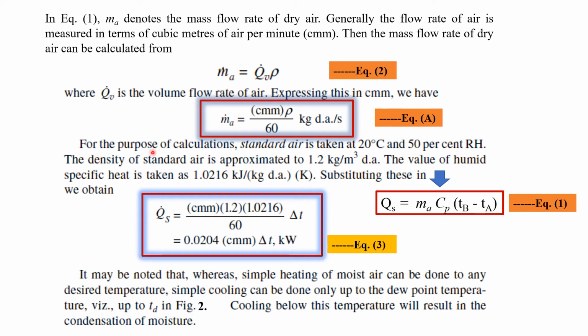Now for the purpose of calculations, the standard air is taken at 20 degrees Celsius dry bulb temperature and 50% relative humidity. The density of standard air is approximated to 1.2 kg per meter cube of dry air. The value of humid specific heat is taken as 1.0216 kilojoules per kg of dry air per Kelvin. So substituting these values in the expression for sensible heat, Qs equal to Ma into Cp into Tb minus Ta.